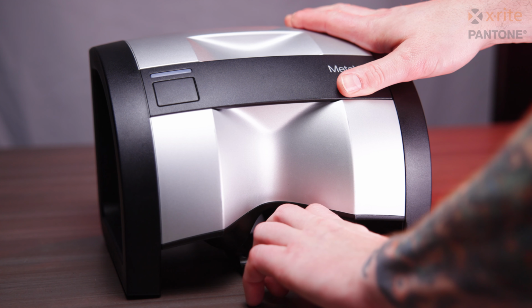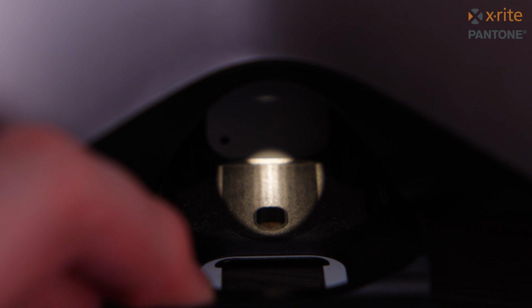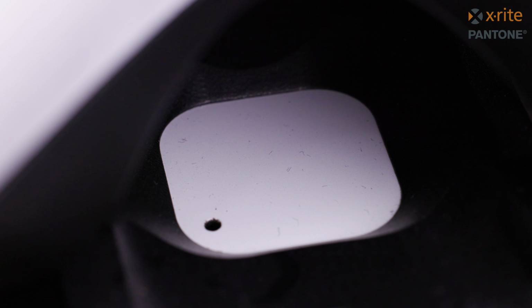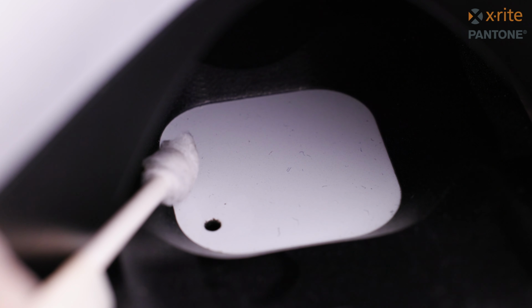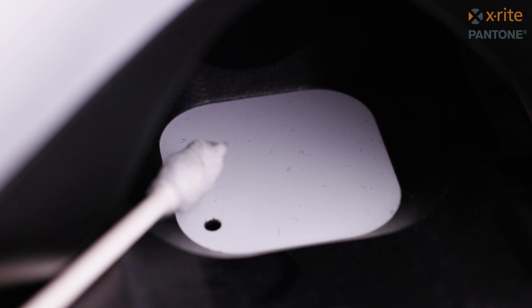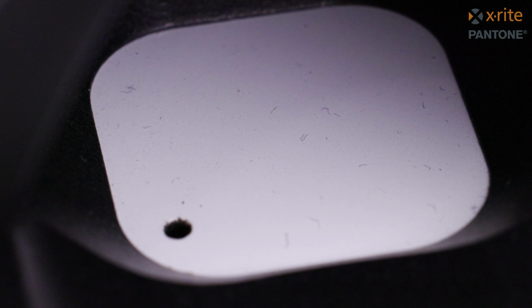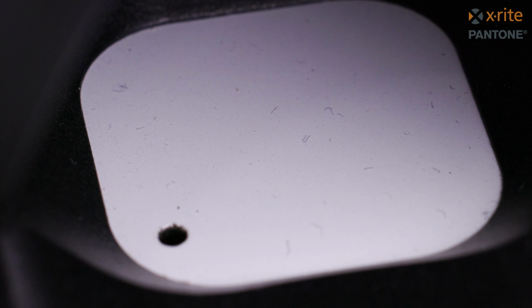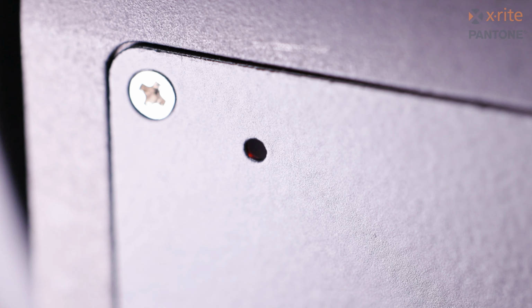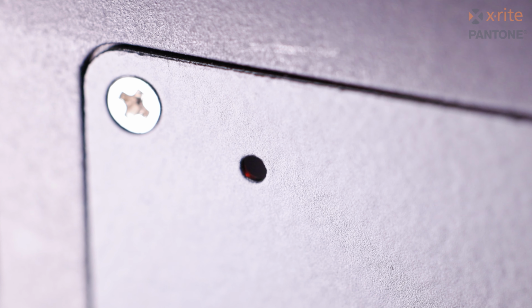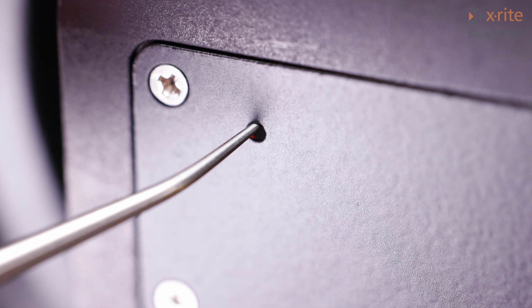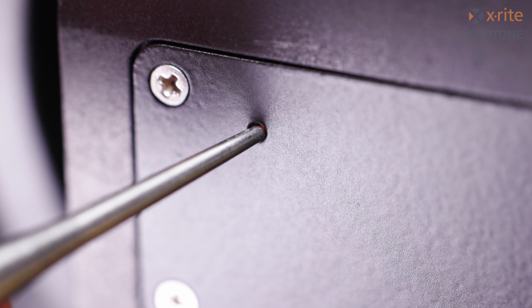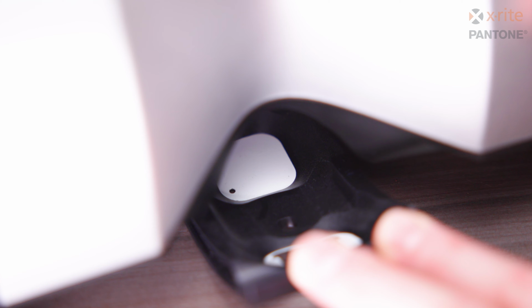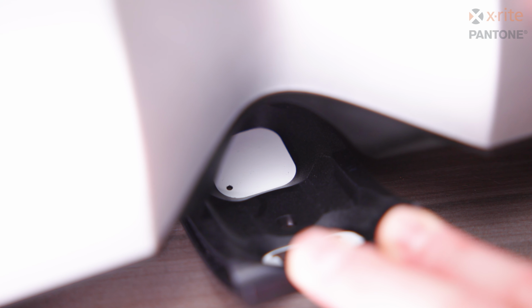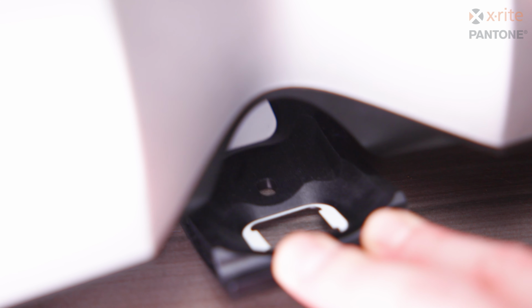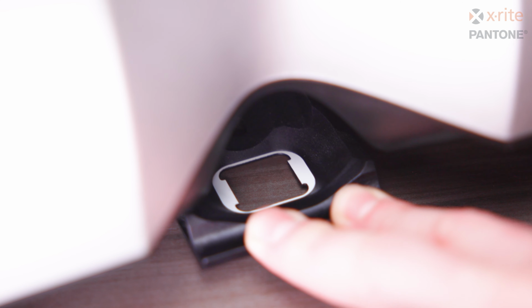Pull the calibration tray forward and rotate to the white square calibration plaque. Inspect the plaque and clean with alcohol to remove any contamination. You will also notice a small hole in the calibration plaque. Take special care to ensure this hole is not clogged with debris. Use a small paperclip or tool to clean the hole if necessary. After the white square calibration plaque has been cleaned, push the calibration tray back to the target window position.